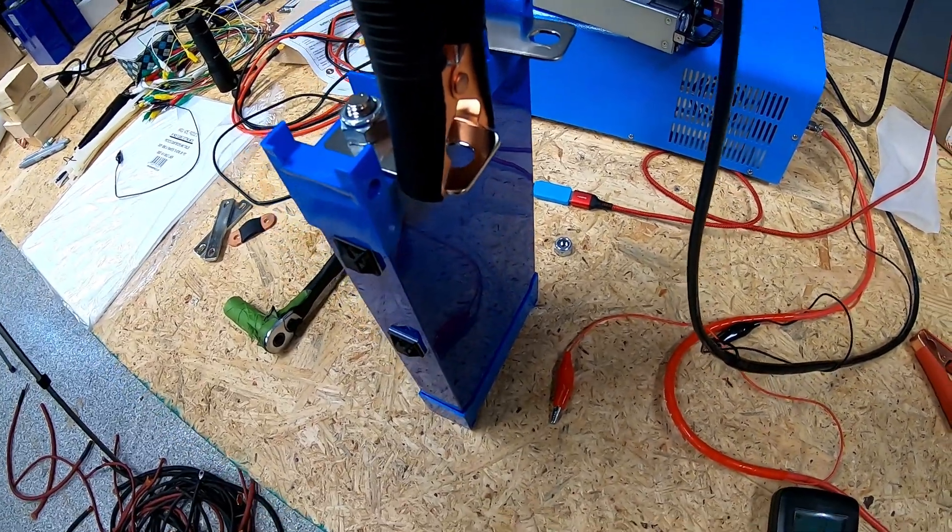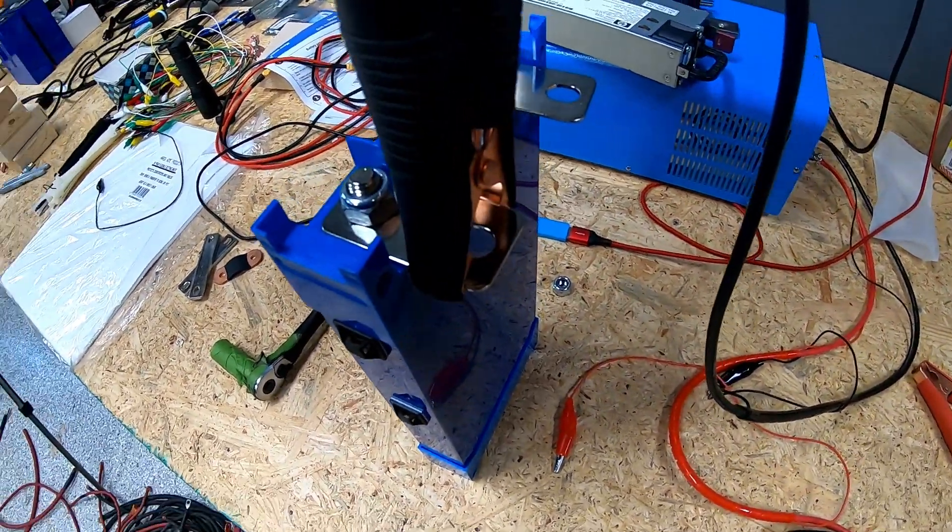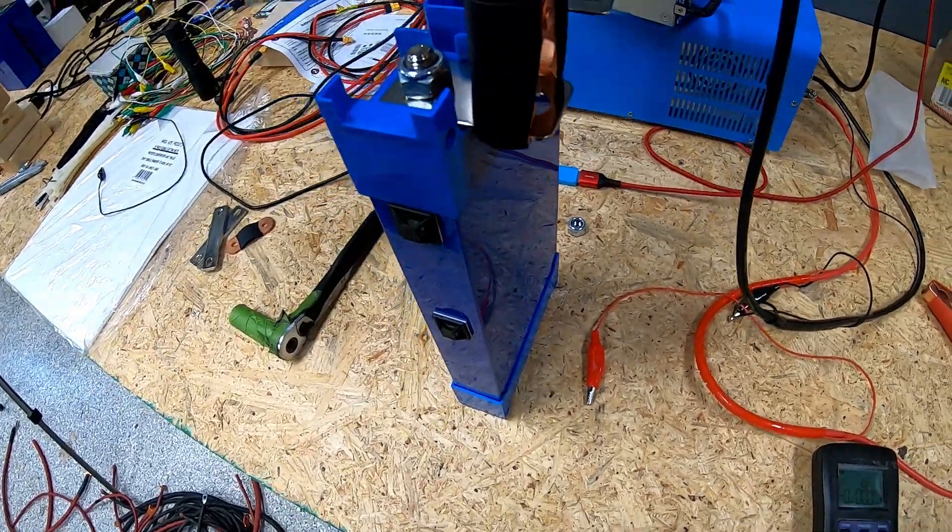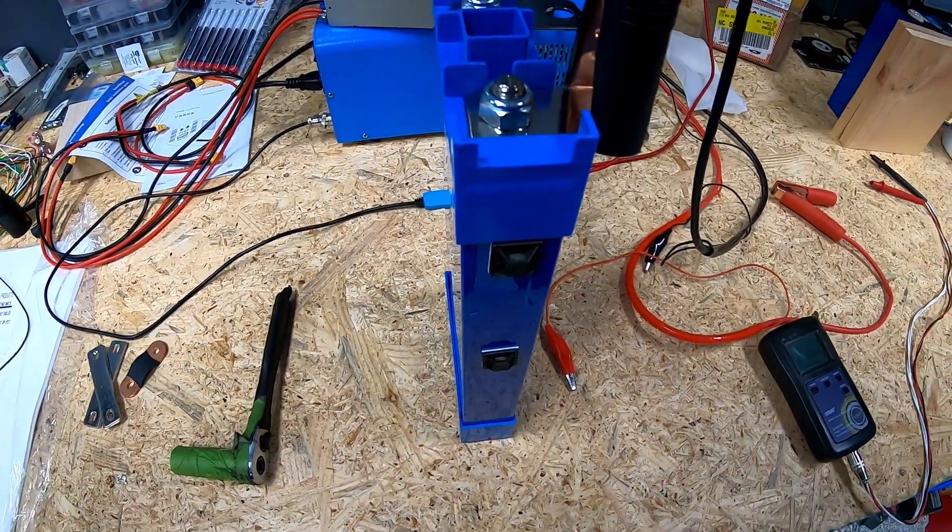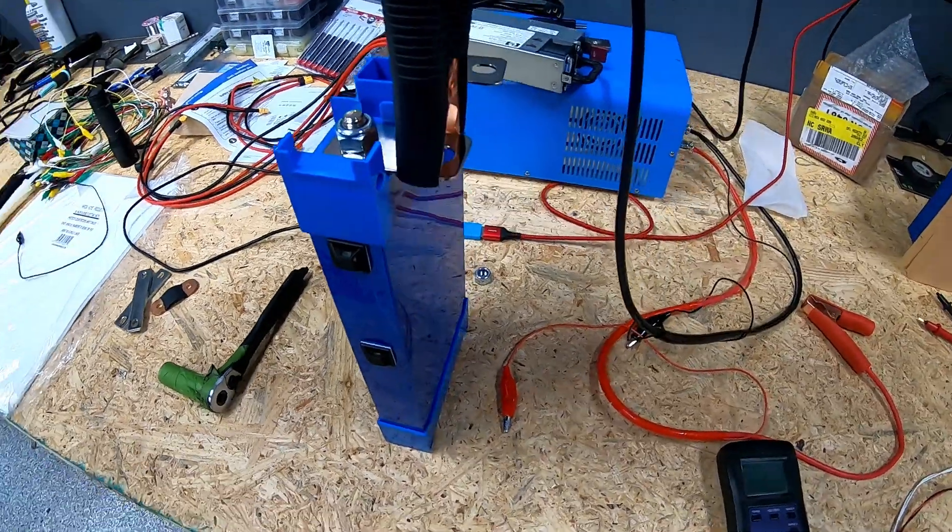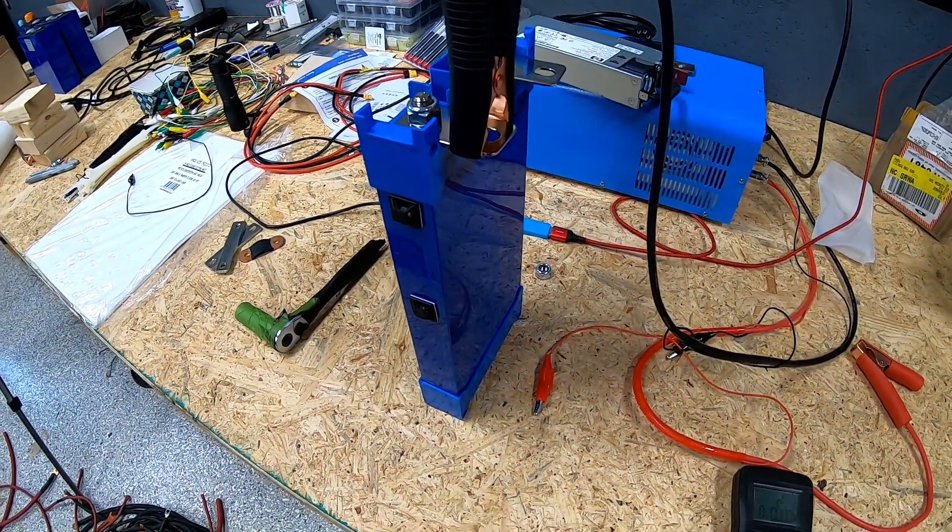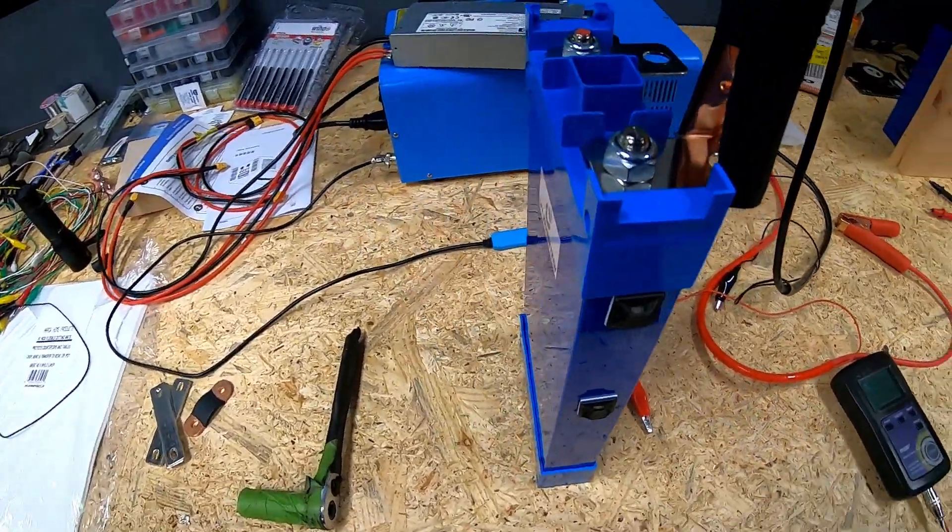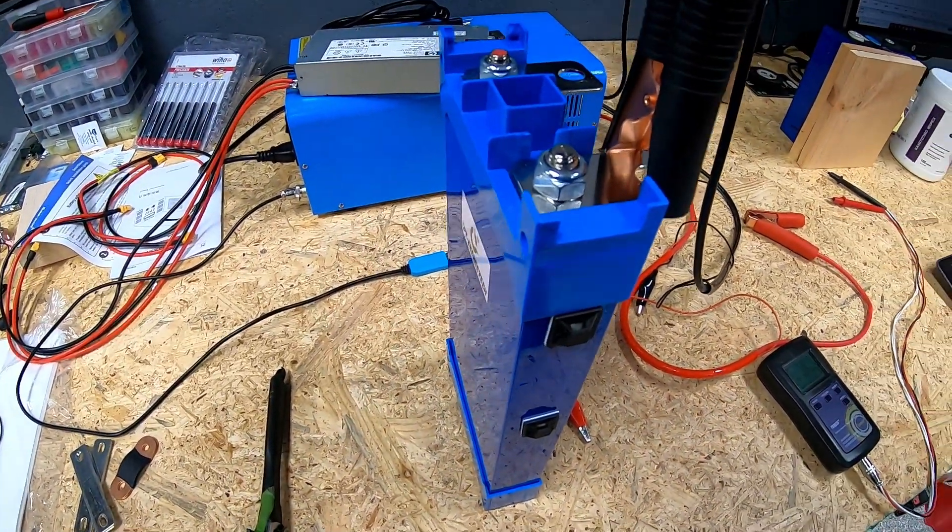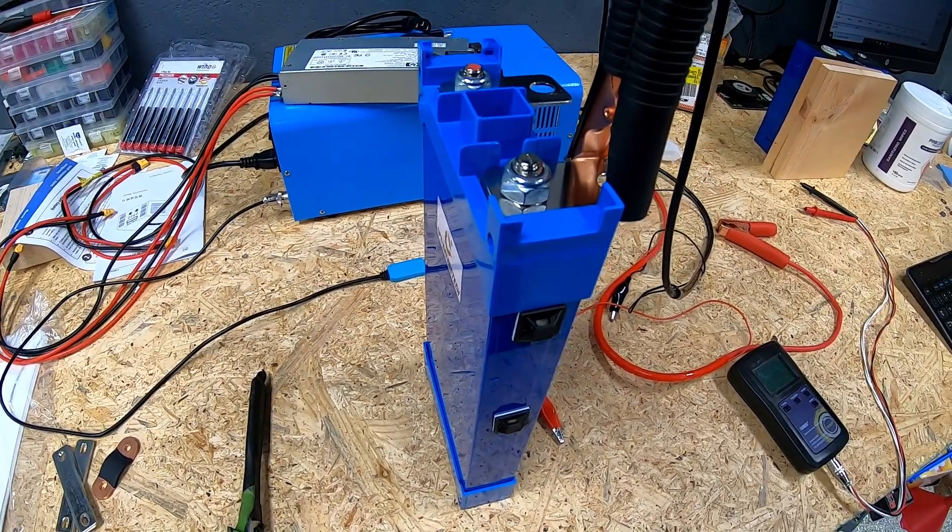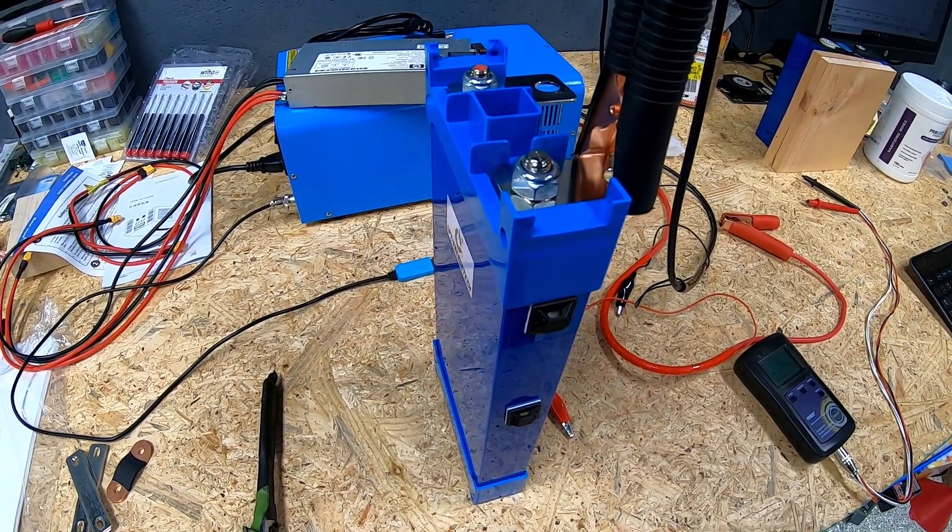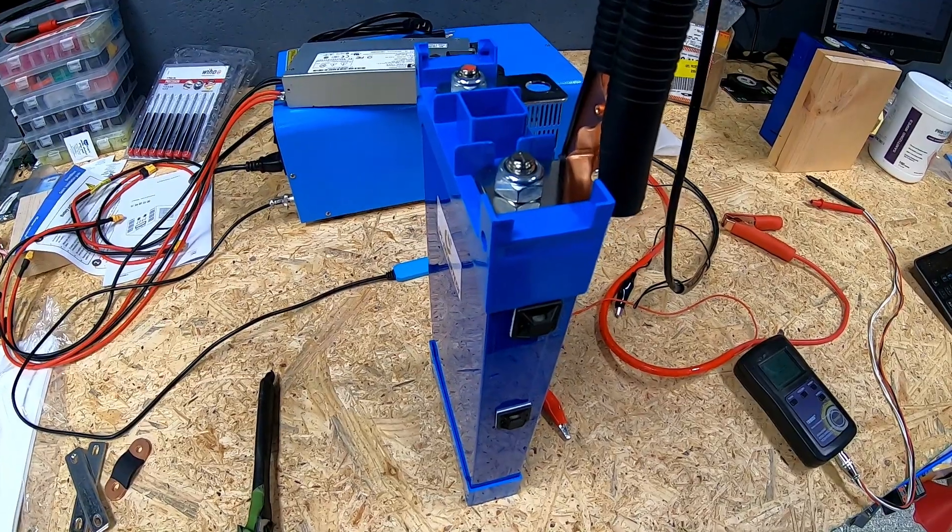These were in service for right at 10 months before they were removed, so they've had roughly about 300 cycles on them. They were used every day, rain or shine. If it rained outside we did run the house partially off of the battery bank and then recovered that charge when the sun came back out again.